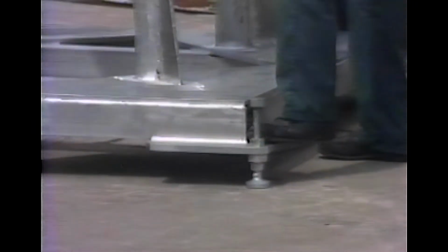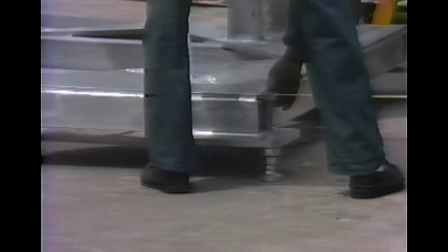Although in an actual system, 3 cables would be used in a 3-phase system, the tests performed at Brookhaven use 2 cables in a single-phase circuit. Each cable will carry a rated power of 333 MVA, corresponding to 1,000 MVA on a three-phase basis.